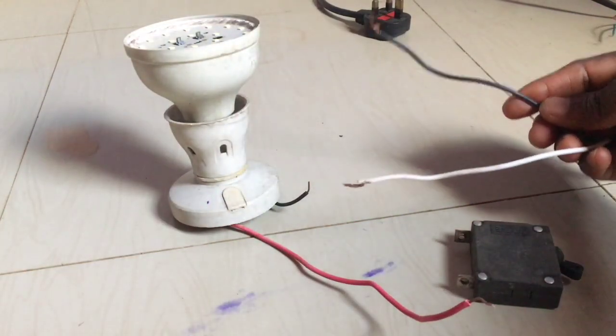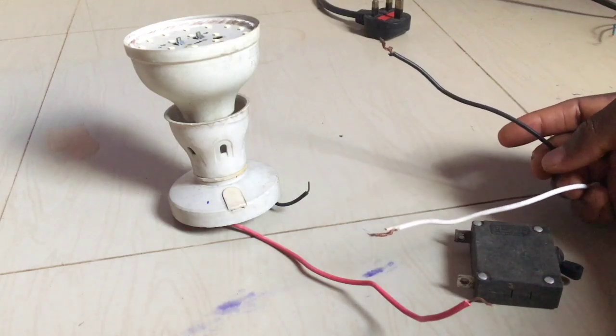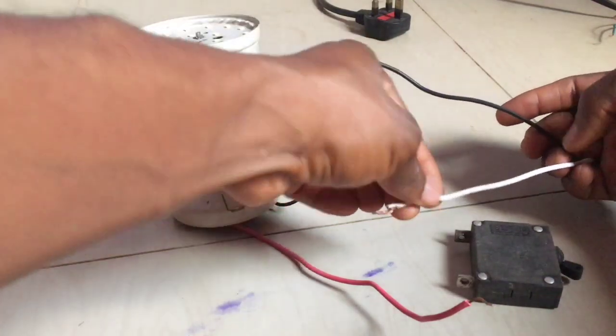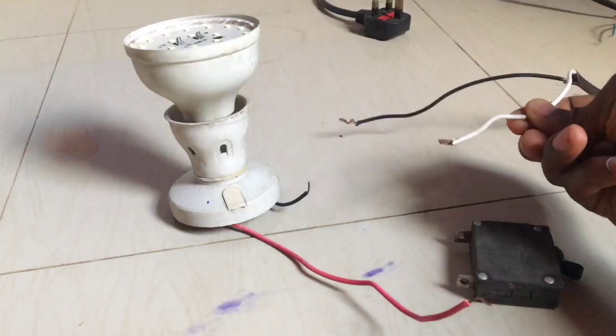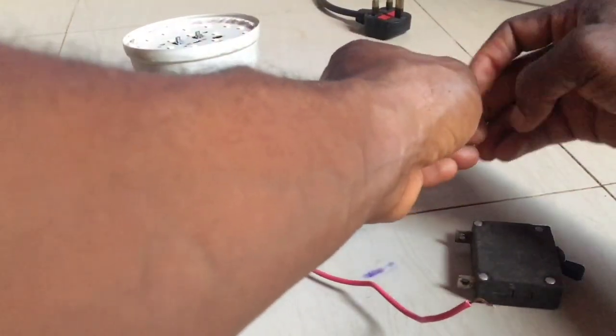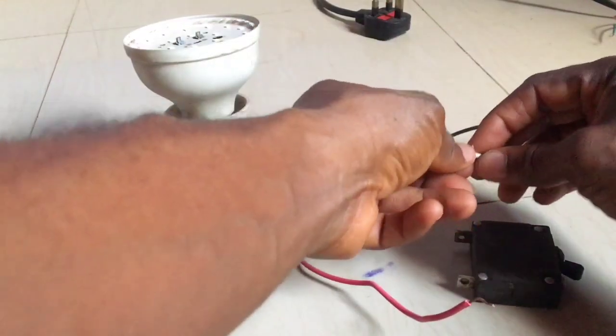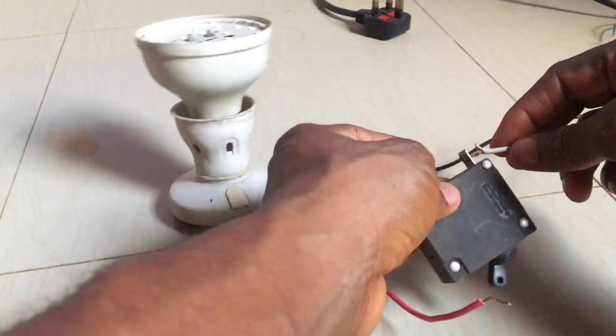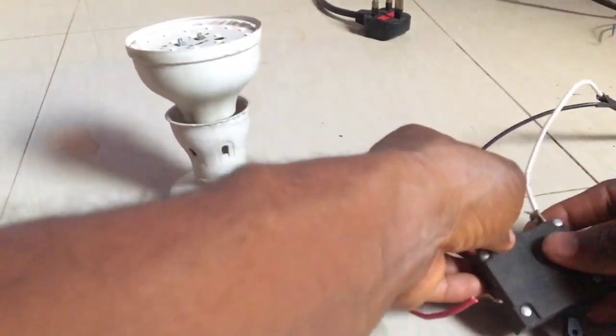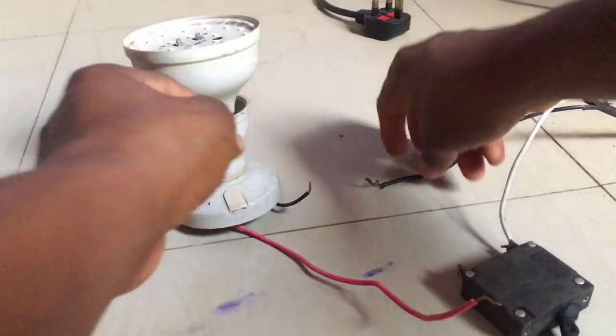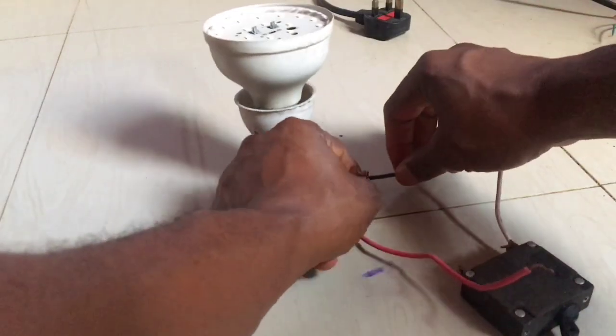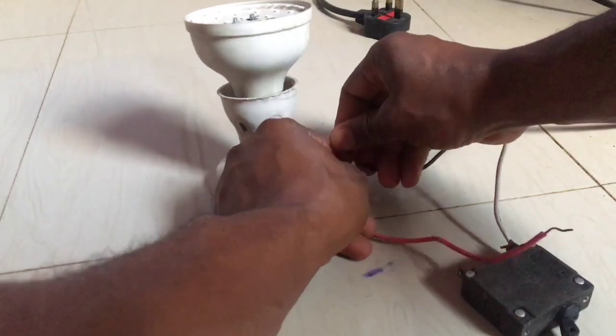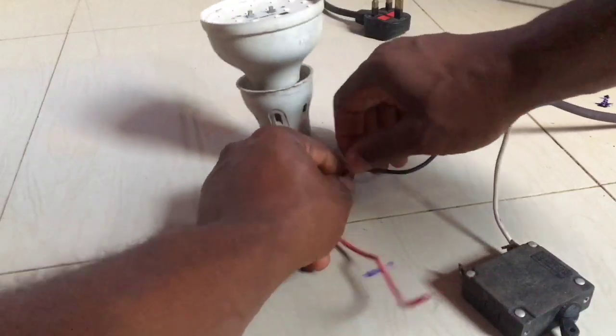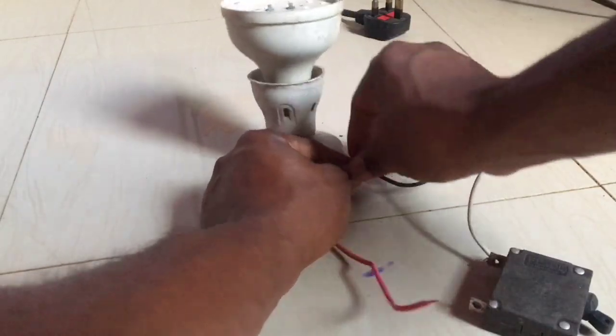So this is how the connection goes. This is from your distribution board, red and black, live and neutral. This is my red. So from the distribution board, live comes straight. Remember, this is not energized, please. That is why I'm able to touch it. From the distribution board, live goes straight to the common terminal of the switch. No joining. Then black from the distribution board goes straight to the neutral terminal of the lighting point.